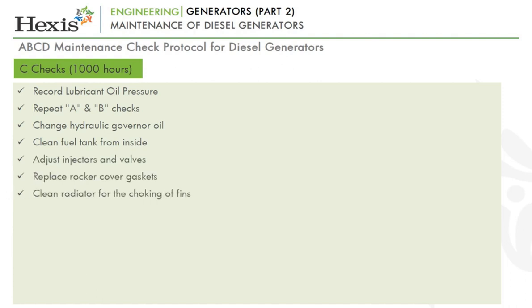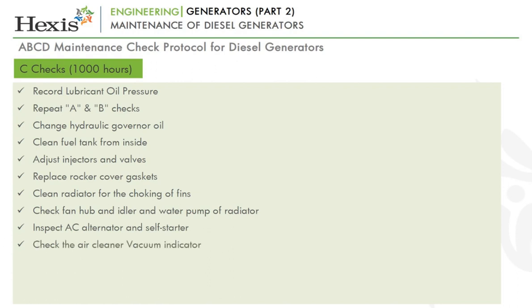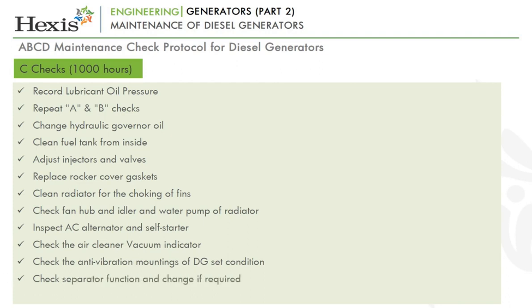Clean radiator for the choking of fins. Check fan hub and idler and water pump of radiator. Inspect AC alternator and self-starter. Check the air cleaner vacuum indicator. Check the anti-vibration mountings of DG set condition. Check separator function and change if required. Check the condition of static potentiometer and EDC, that is, electronic diesel control.